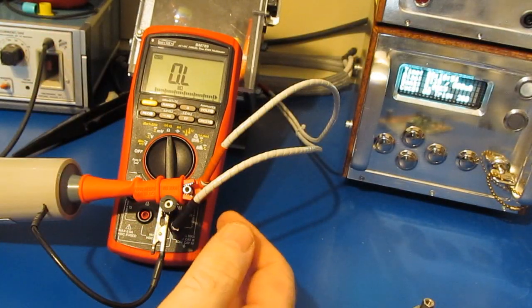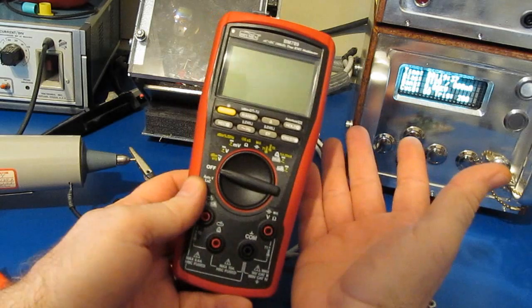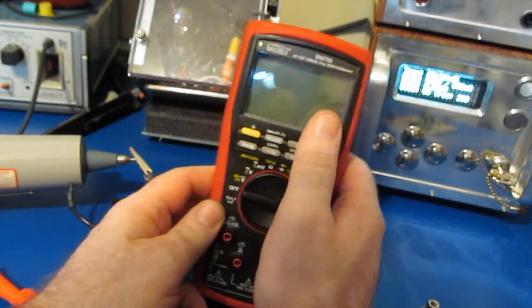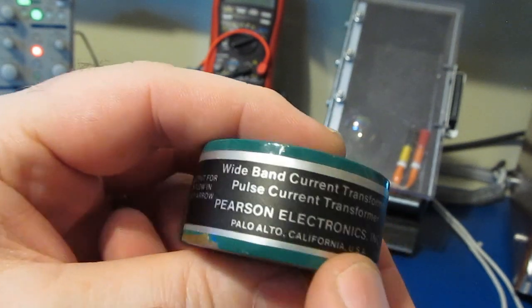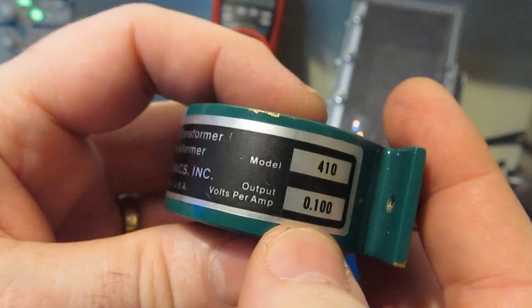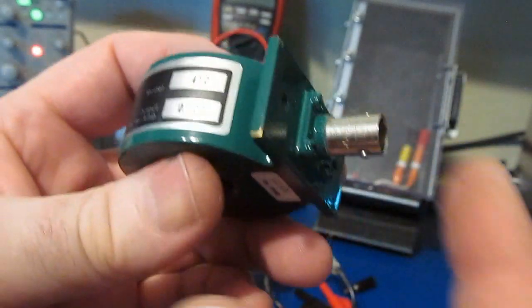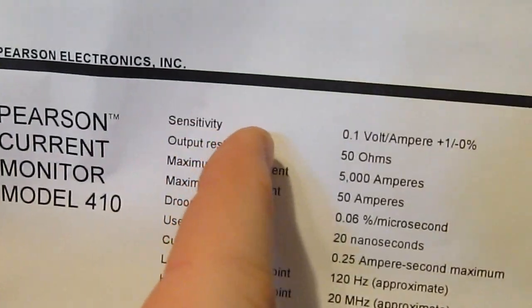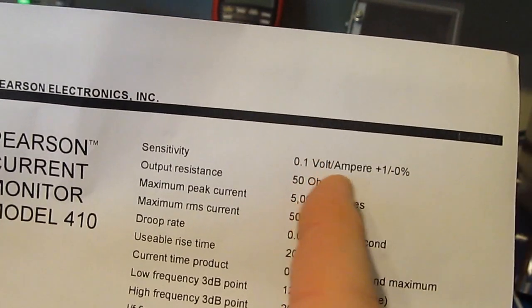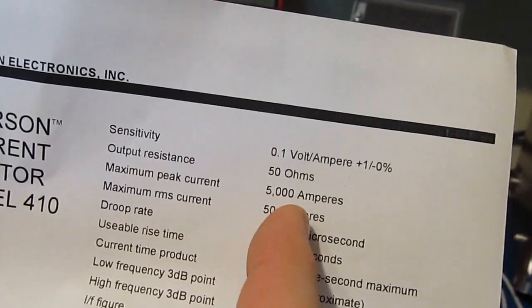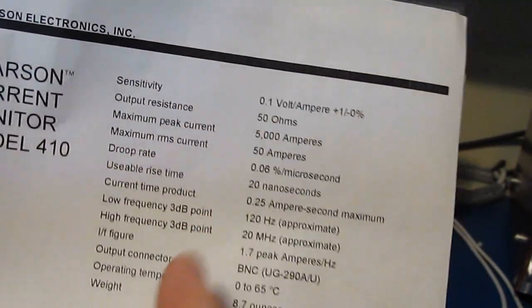So what would happen if the meter were to break down? In this case, we're talking about 1,000 volts that's limited by a 2 ohm internal source resistance, plus our cabling. But essentially, we're talking about a peak of 500 amps. Now our little Tektronix current probe cannot measure that. So in order to look at these higher currents, we're going to use this Pearson pulse current transformer. This particular one is a model 410. You can see it outputs 0.1 volts per amp, and that's into a 50 ohm load.